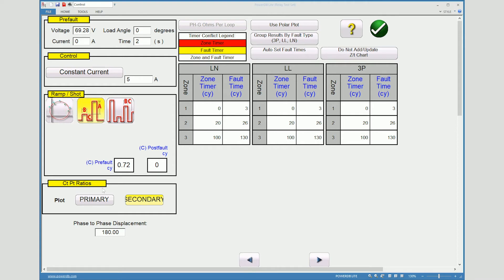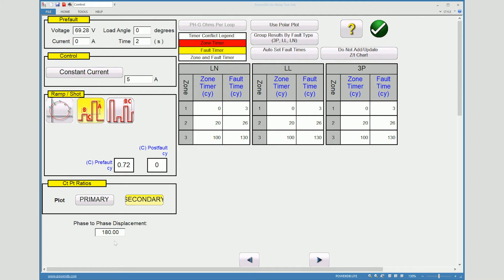We have the option to view this information with CT ratios inputted for primary or secondary. For this place we're doing secondary. Our phase to phase displacement is 180 degrees apart from the two phases that were chosen. Whether it be A to B fault, B to C fault, or C to A fault.